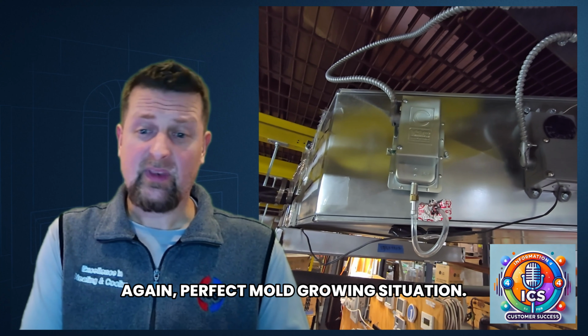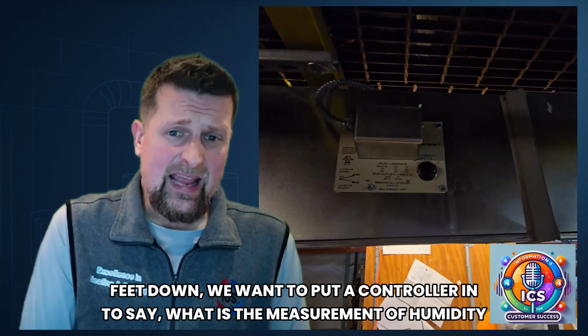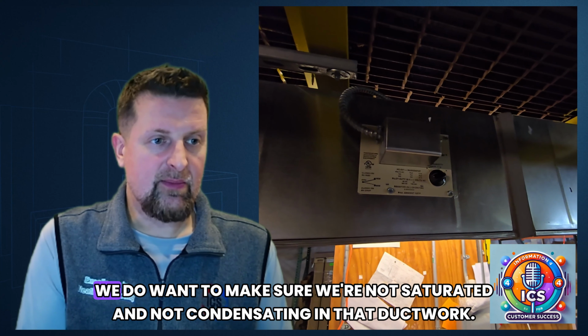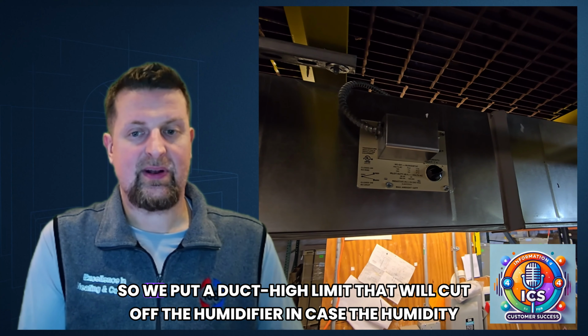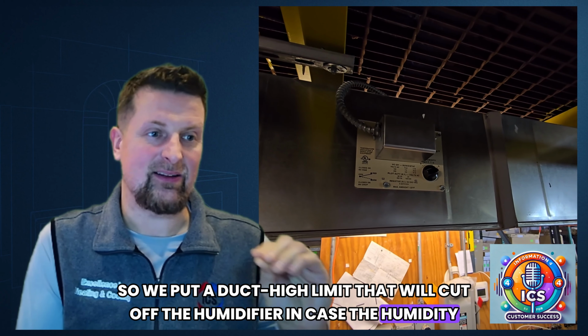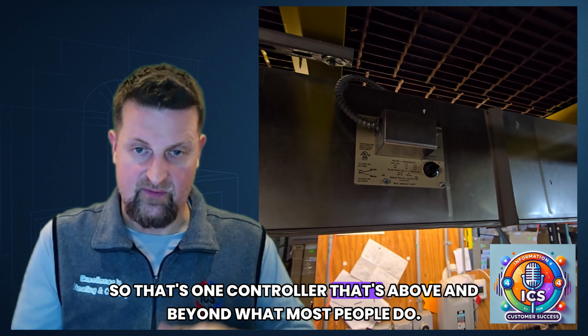A duct high limit. Now, an air proving switch and humidistat is what probably 99% of your average HVAC companies do. Everything I'm about to talk about now, you have to be extremely careful. A lot of companies do not do these, but they should. A duct high limit is a controller that is a little bit further back from your steam distributor. Your steam distributor is the point of injection of the steam inside your ductwork. Steam flows a certain direction with the ductwork, and a little bit further down, depending on the manufacturer, depending on the scenario, at least 4 feet to 10 feet down, we want to put a controller in to say, hey, what is the measurement of humidity inside the ductwork? We do want to make sure we're not saturated and not condensating in that ductwork. So we put a duct high limit that will cut off the humidifier in case the humidity gets a little bit too high in the ductwork.